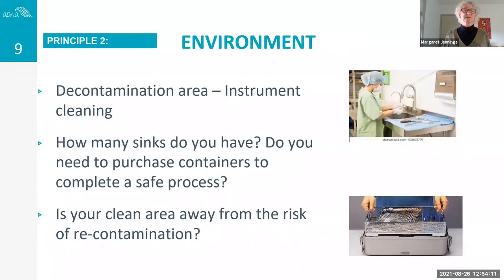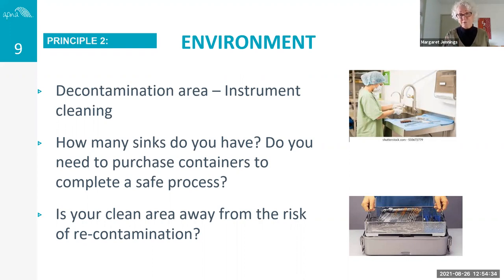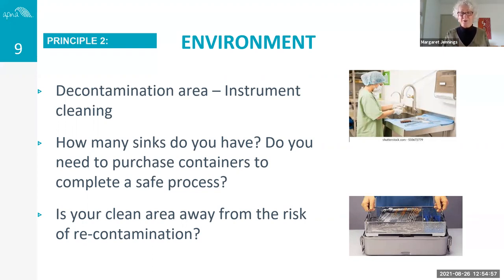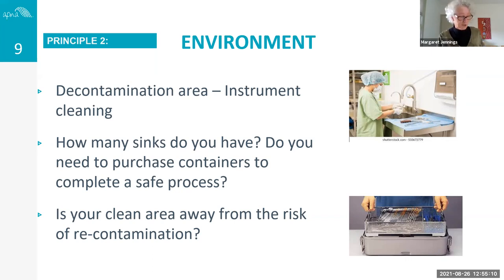From the time you're washing instruments, the area becomes contaminated. I don't want anyone within a meter or two of me, because as I'm scrubbing I'm sending droplets into the air that land about a meter out. If you have boxes of gloves or paper towel on the wall right in front of you, they will be contaminated every time. You need to wipe over a meter out every time you process instruments. We don't use tiles and grout in that area much anymore — it tends to be smooth splashbacks. That means being very thorough with detergent and paper towel unless you have detergent wipes.